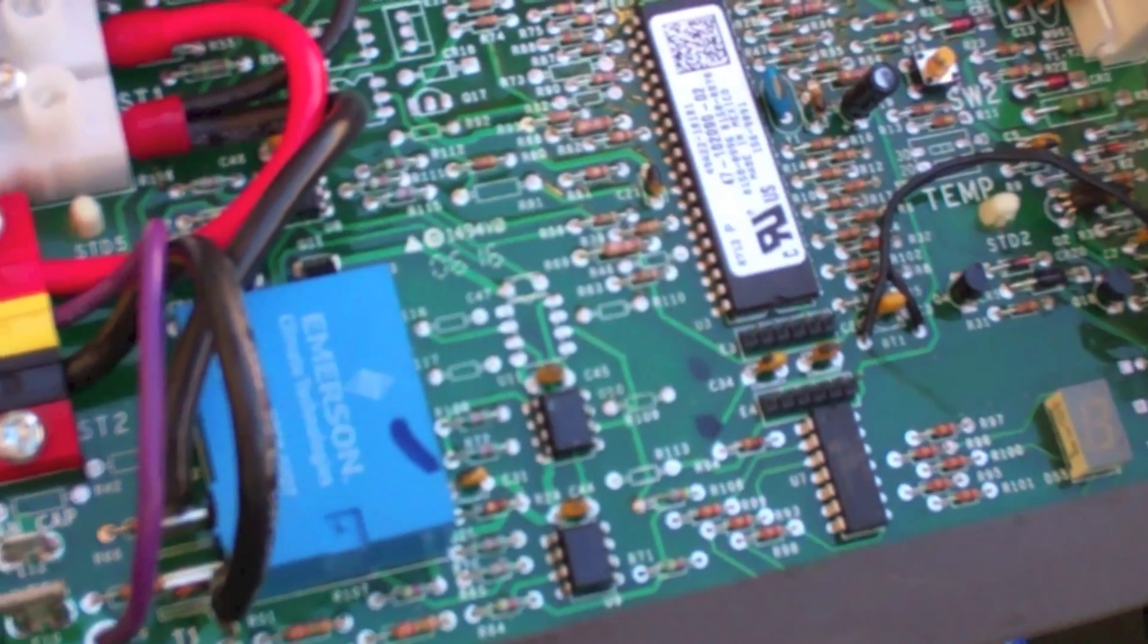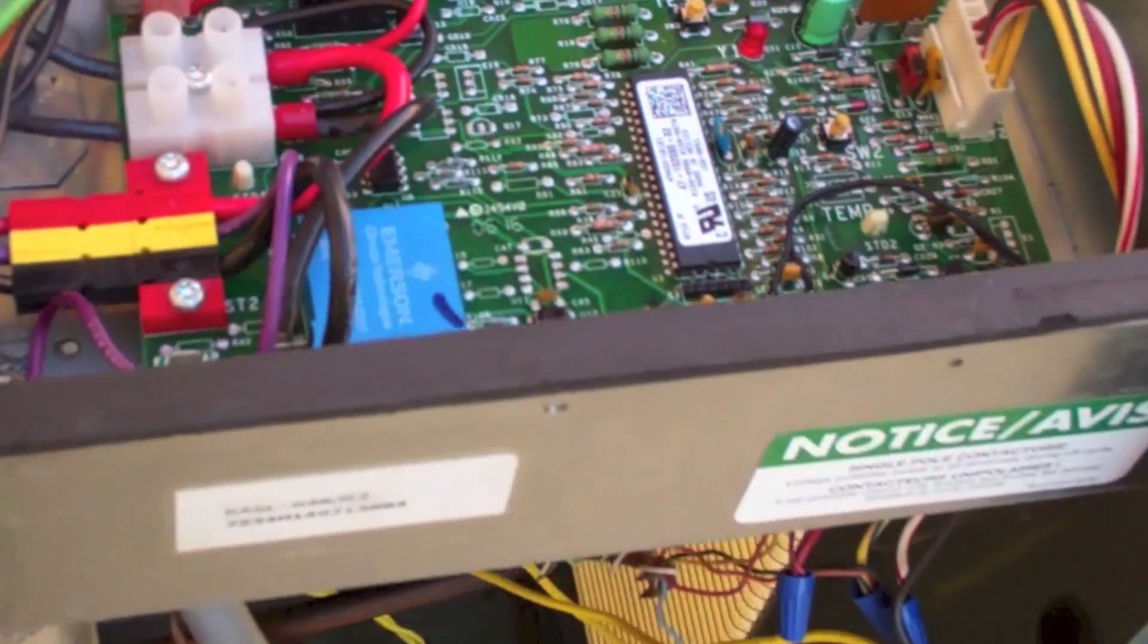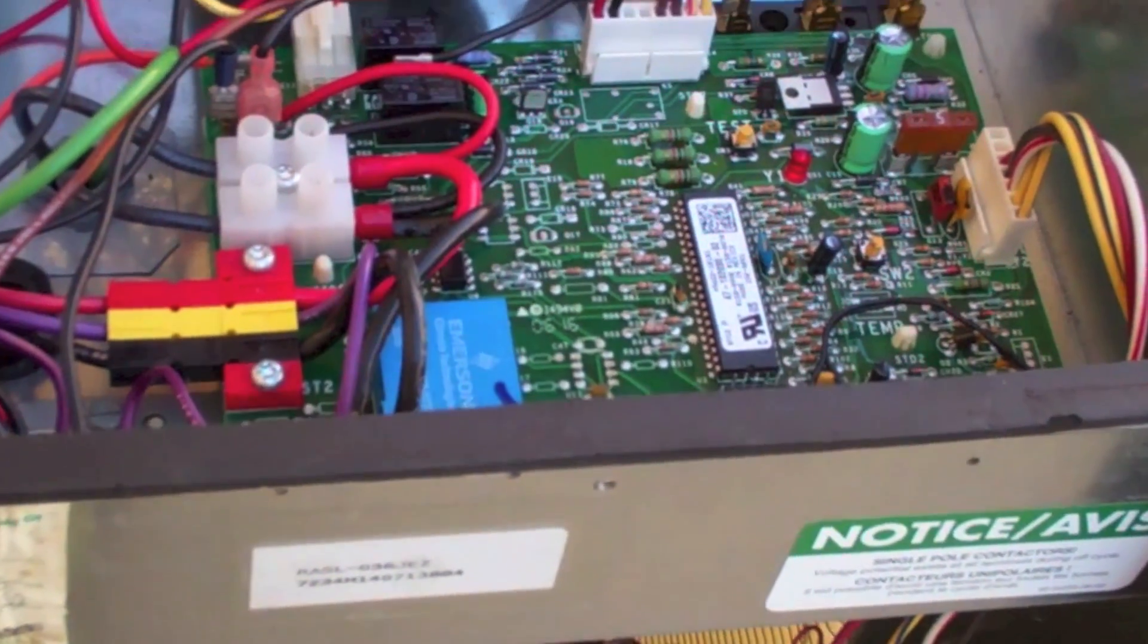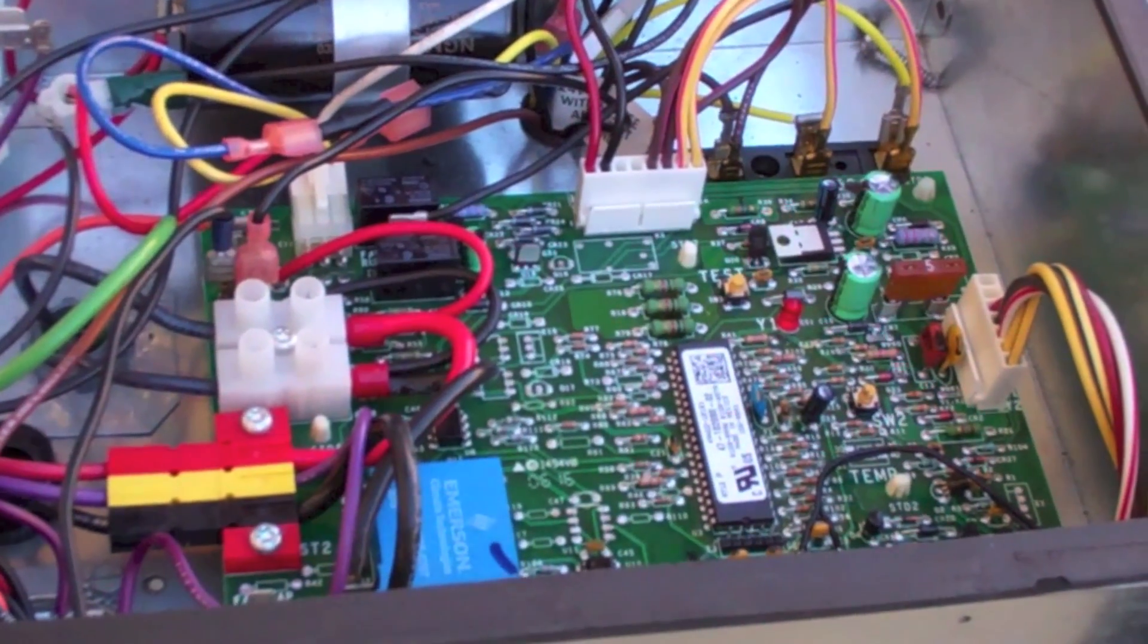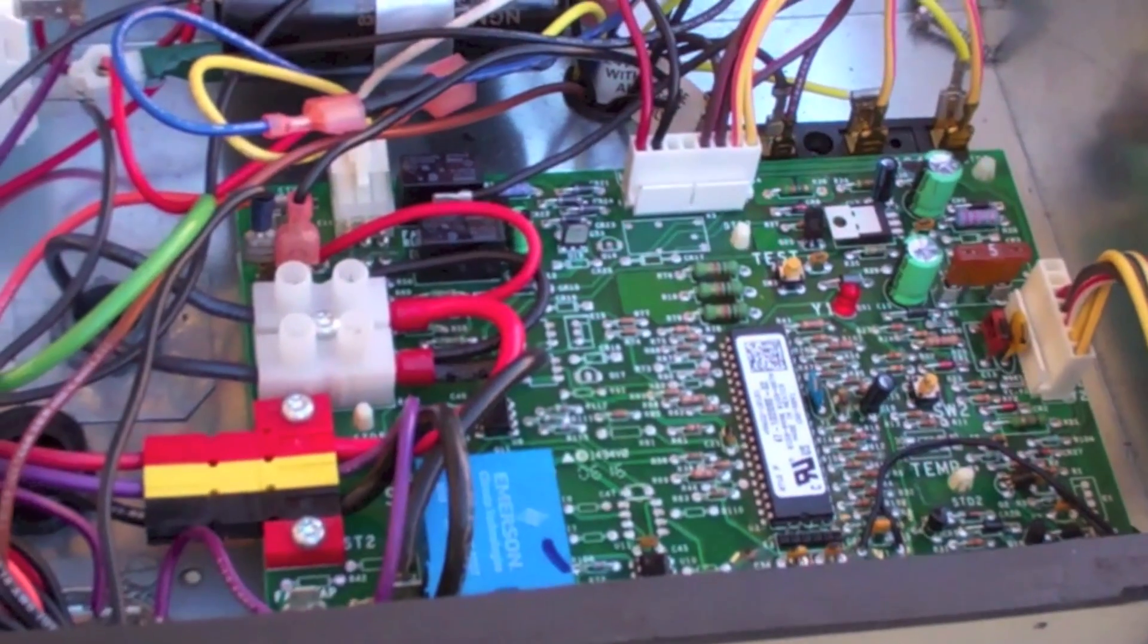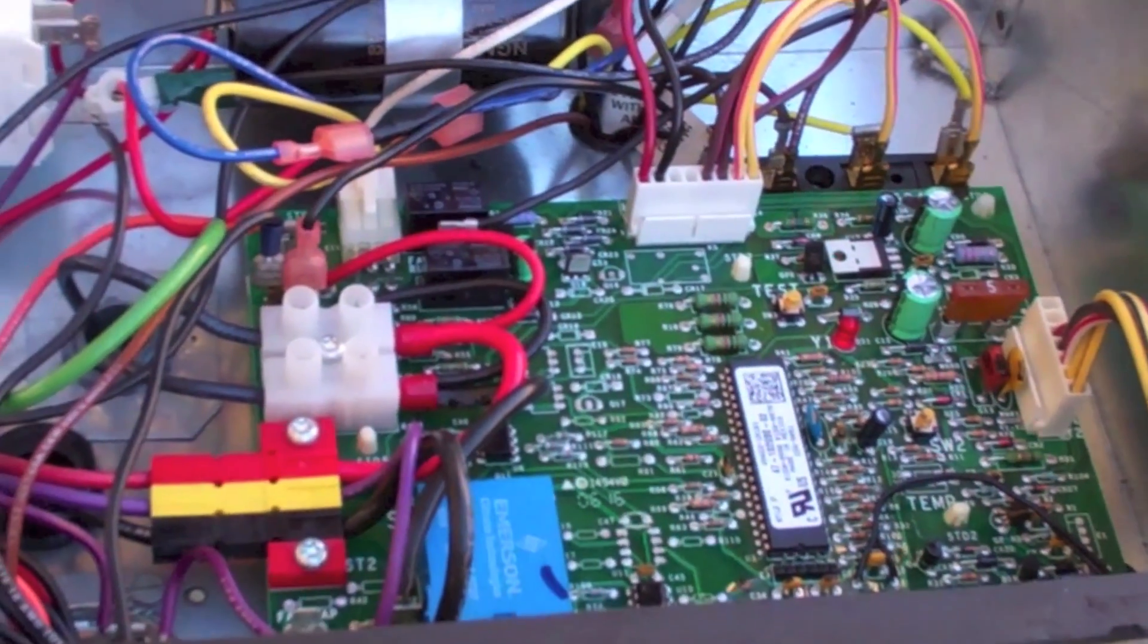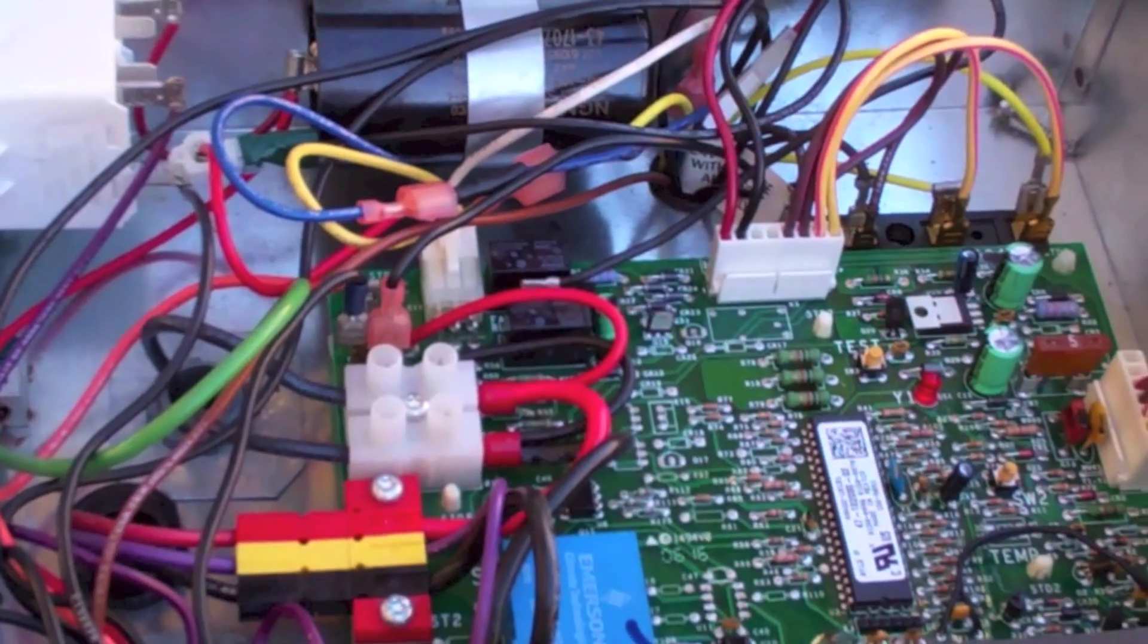It was because of the optical sensor, which sees the light from the compressor going on and off. There's arcing - the optical sensor is going to time it in the waveform where the unit turns on and shuts off at zero volts or pretty close to zero volts, so there's no arcing of the contacts, very minimal.